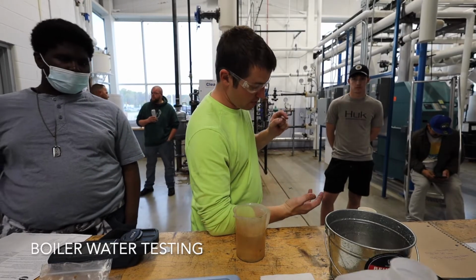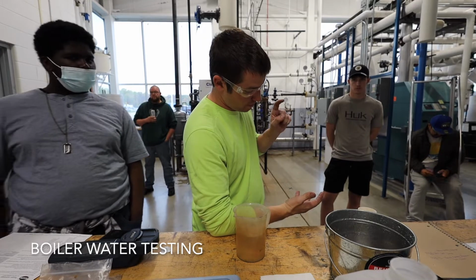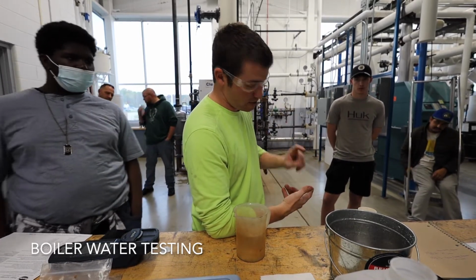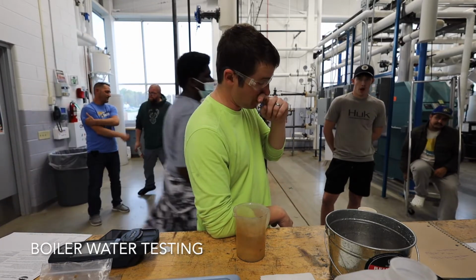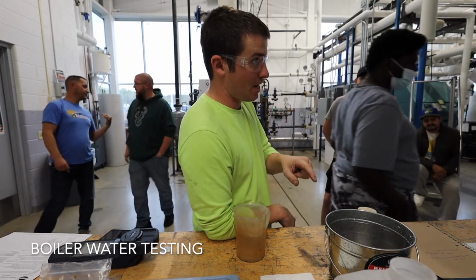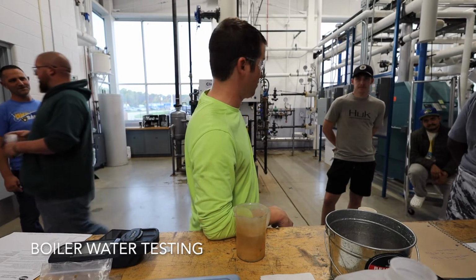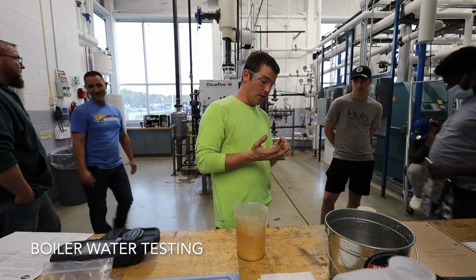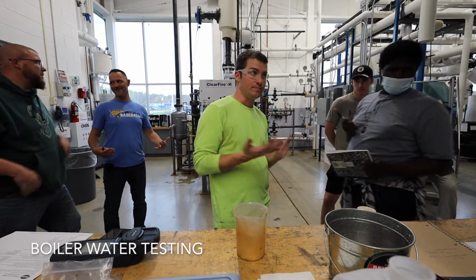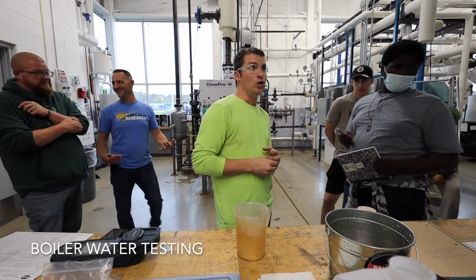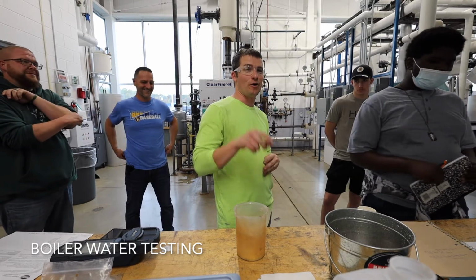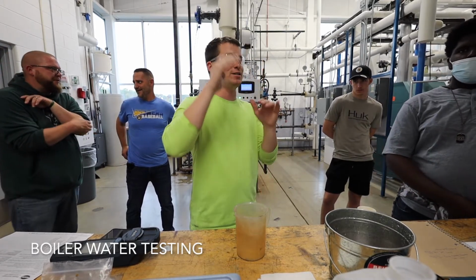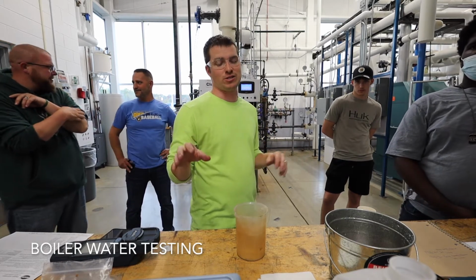Normally you would test conductivity, sulfite, a polymer or internal treatment, and alkalinity. And in your case, because we're testing the DEHA, which is the active thing we want to test for on this product, we're testing the feed water. All we're going to do in your boiler is conductivity and alkalinity. No pH. No pH because, if the alkalinity is where it should be, the pH is going to be where it needs to be. pH and alkalinity directly impact each other. It's not worth the chemistry lesson to try to explain that.